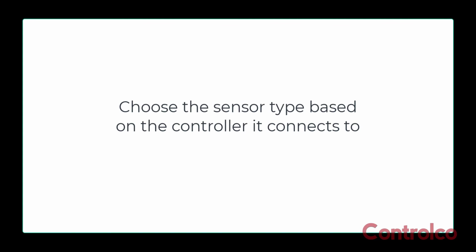When you pick out a temperature sensor, probably the most important part of picking one out, other than the shape and the mounting consideration, is it going into a pipe? Is it going into a piece of ductwork? Is it hanging on the wall? Is it going to be surface mounted on a pipe so that you don't have to drill a hole in the pipe to sense the fluid moving through the pipe? Is the compatibility with the controller that you're going into.